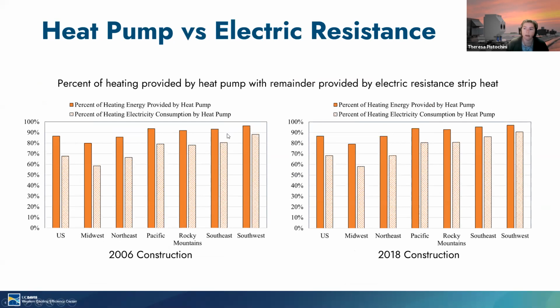The balance is provided by electric resistance heat. The fraction of heating provided by the heat pump mode was lowest in the coldest climates, the Midwest and Northeast, where approximately 80% of the heating capacity was provided by the heat pump and 20% by electric resistance. Even though loads are significantly different between 2006 and 2018 home vintages, the percent of heating provided by the heat pump is similar because the heat pump capacity was auto-sized to meet the design day load of the home.